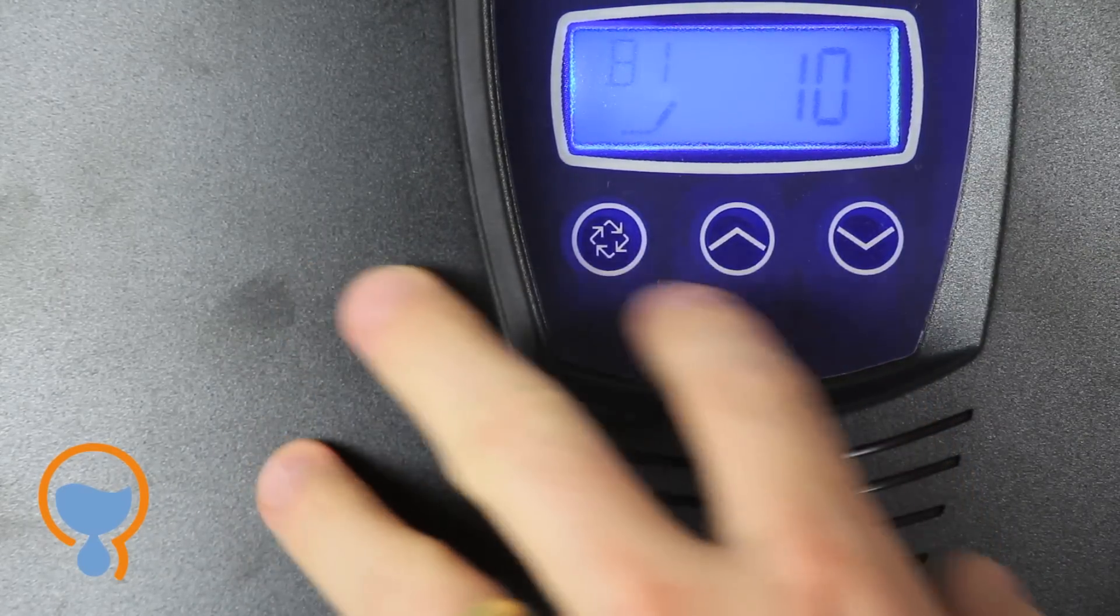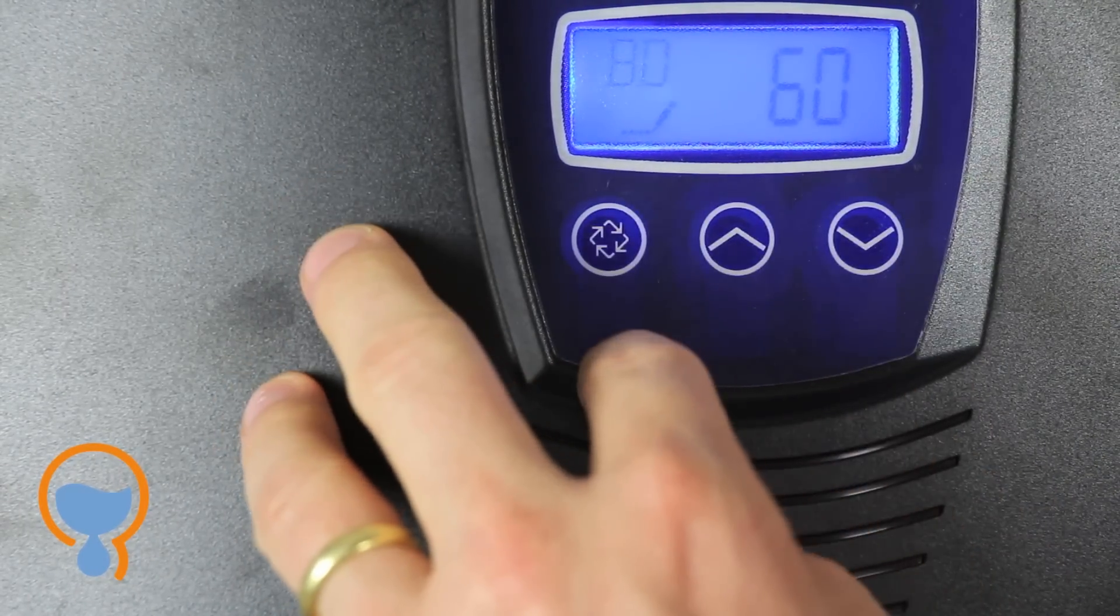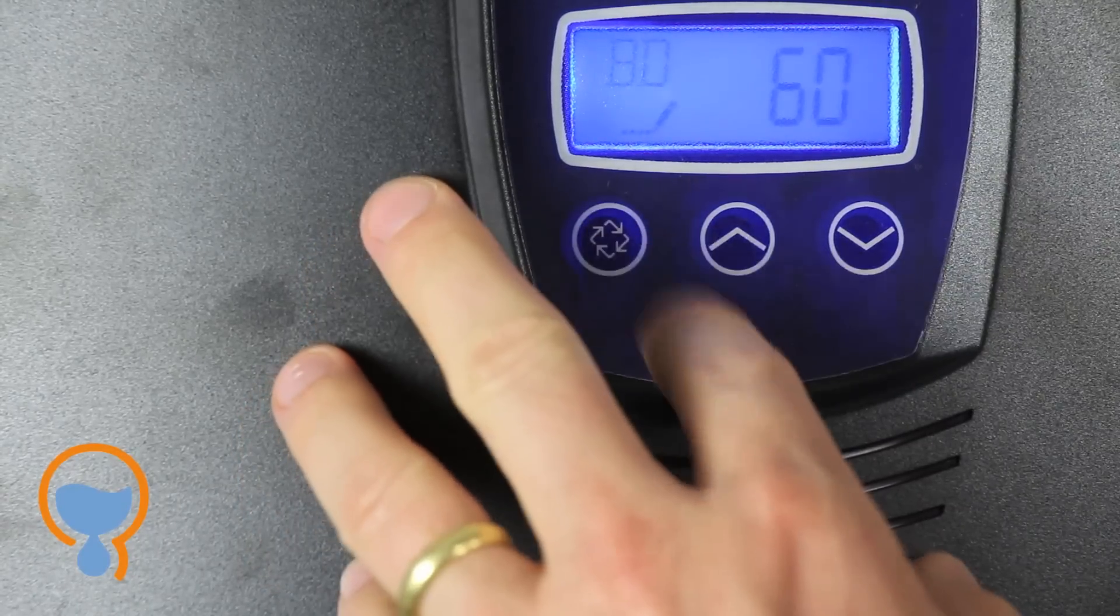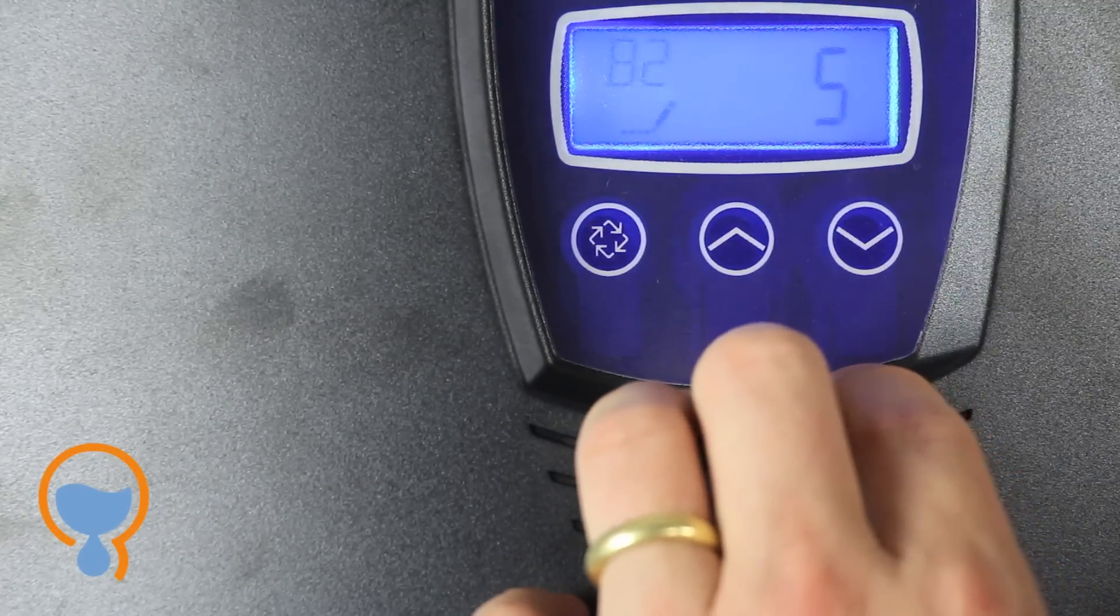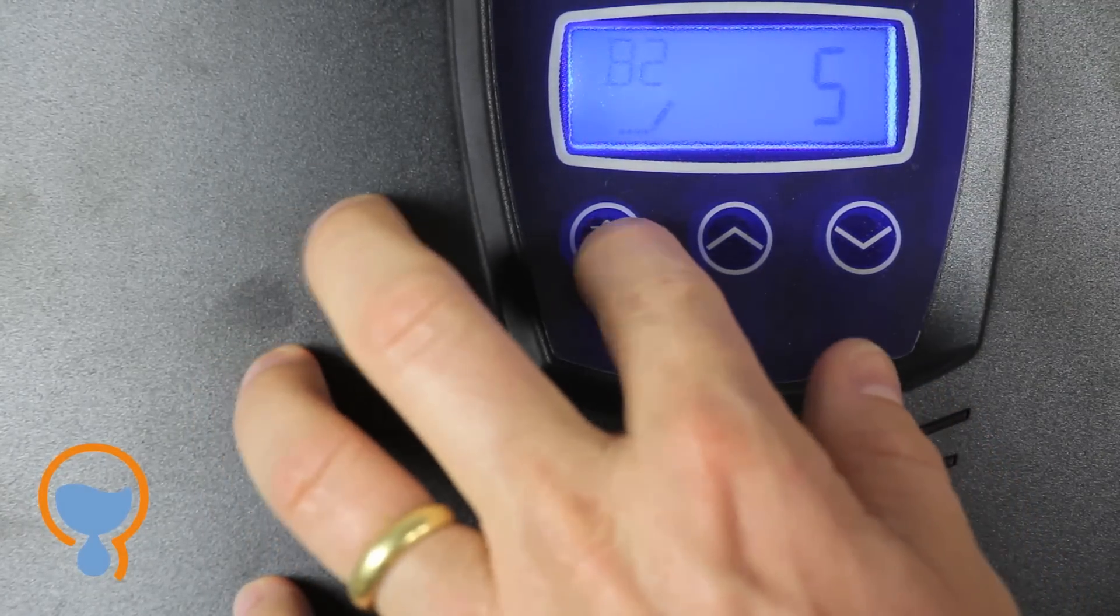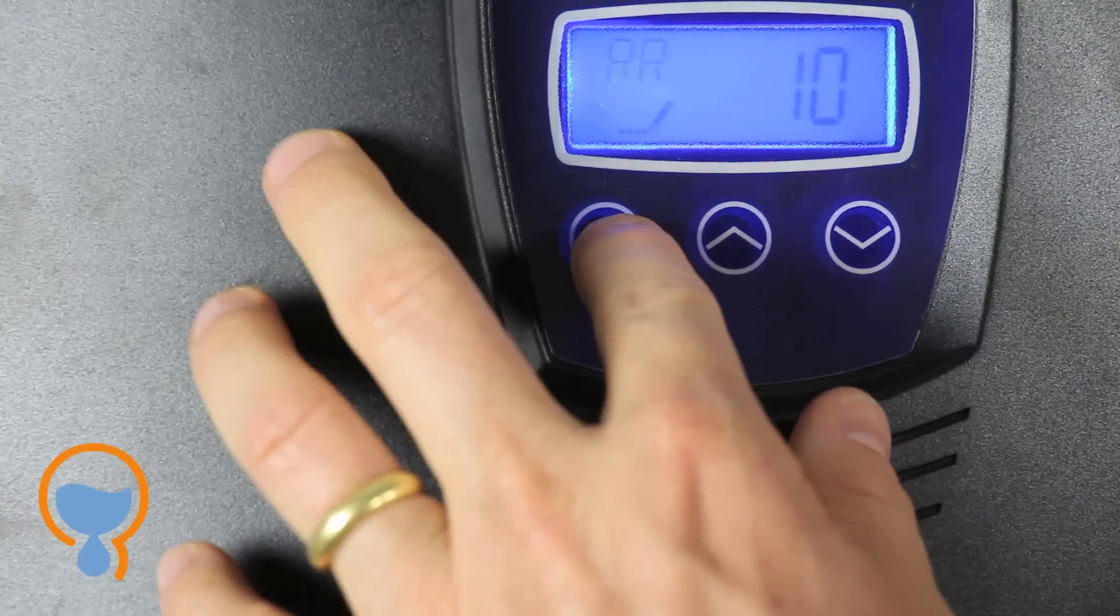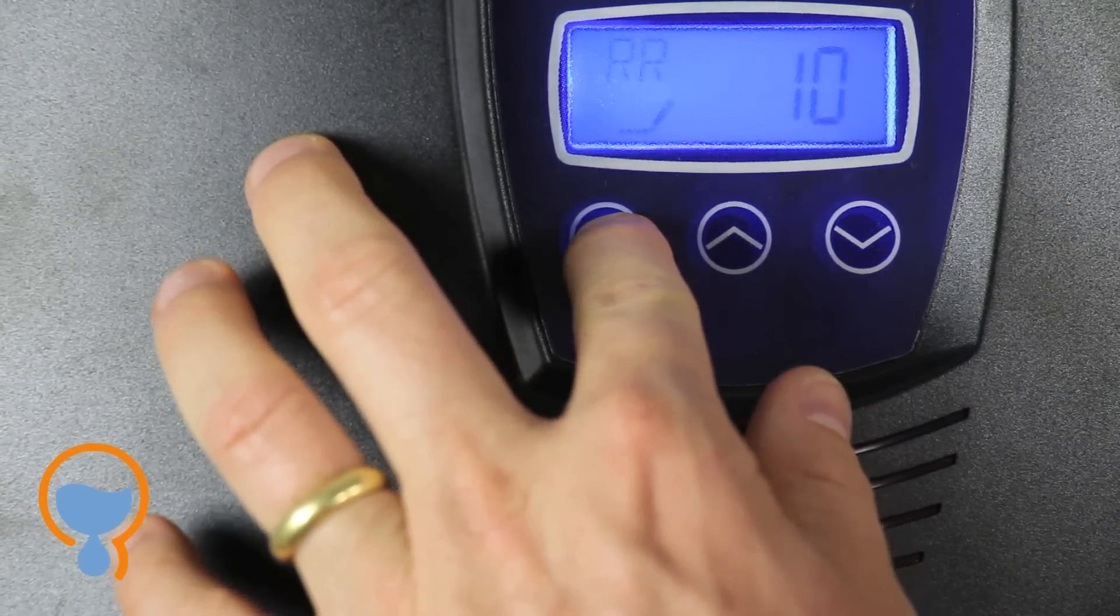Backwash is defaulted to 10 minutes which is perfect. We'll press enter. The brine draw is 60 minutes which again is perfect. We'll press enter. Backwash 2 is 5 minutes. Perfect. We'll press enter on that. Rapid rinse 10. Again, the default is the setting that we want. So 10 minutes we'll press enter on.